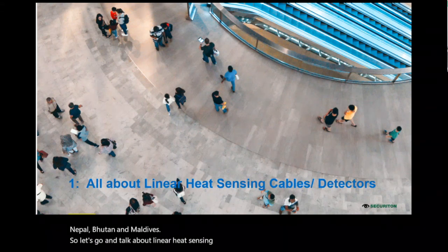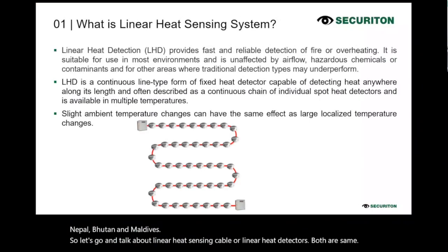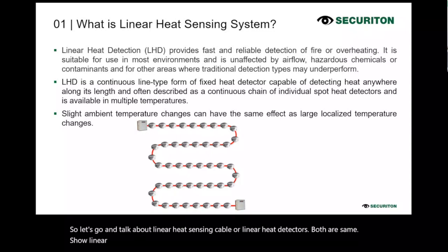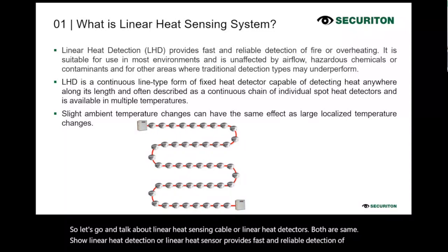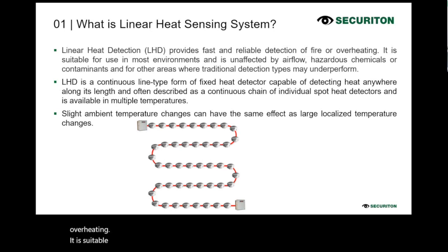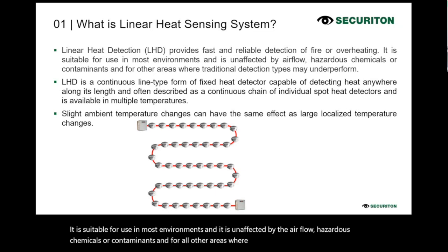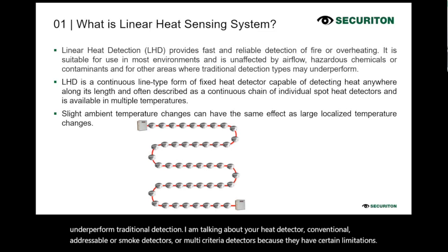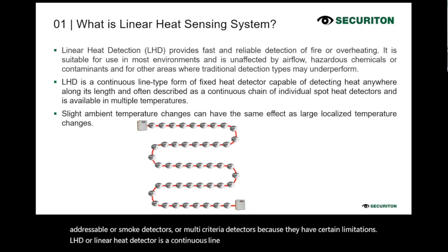So let's go and talk about linear heat sensing cable or linear heat detectors. Both are the same. Linear heat detection provides fast and reliable detection of fire or overheating. It is suitable for use in most environments and is unaffected by airflow, hazardous chemicals, or contaminants, and for all other areas where traditional detection types may underperform. Traditional detection, I am talking about your heat detector, conventional or addressable, or smoke detectors or multi-criteria detectors, because they have certain limitations. LHD, or linear heat detector, is a continuous line type fixed heat detector. It is capable of detecting heat anywhere along its length.